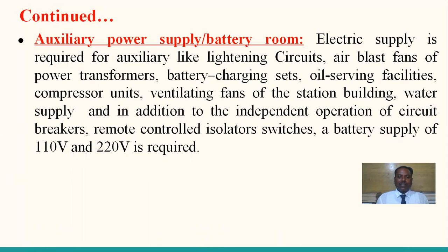The transformer is continuously operated, so overheating is generated and it has to be cooled through huge fans called air blast fans. Also battery charging sets, oil serving facilities, compressor units, ventilating fans of the station building, water supply, and in addition, for the independent operation of circuit breakers and remote controlled isolator switches, a battery power supply of 110 volts or 220 volts is required.